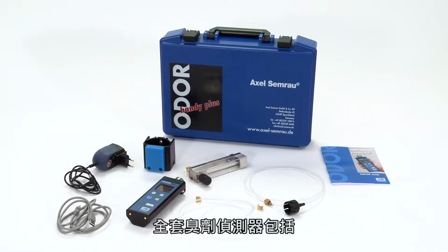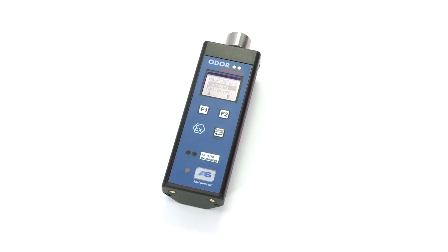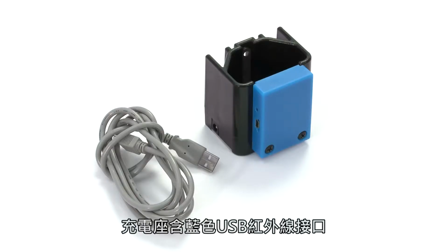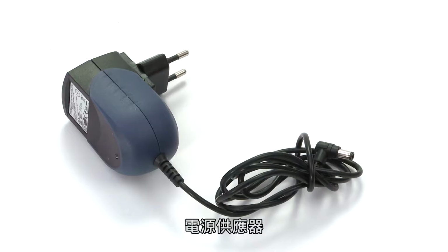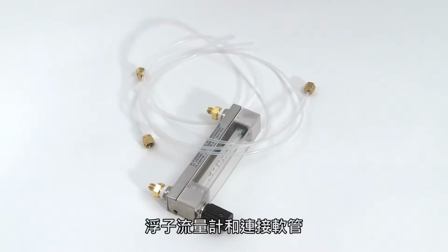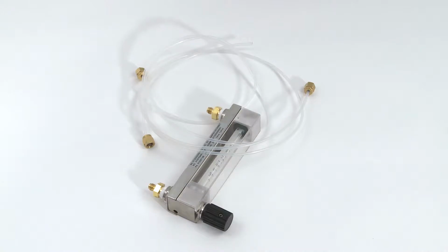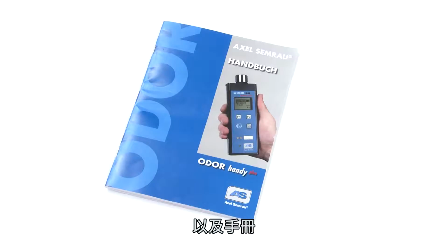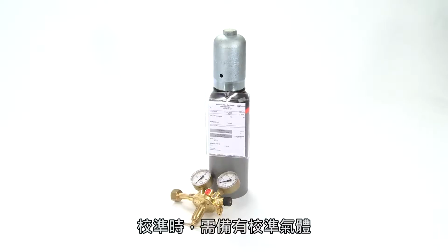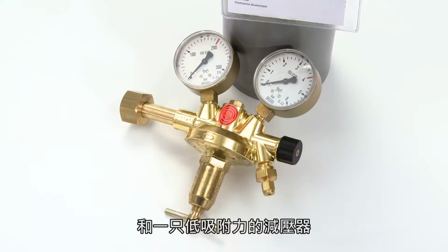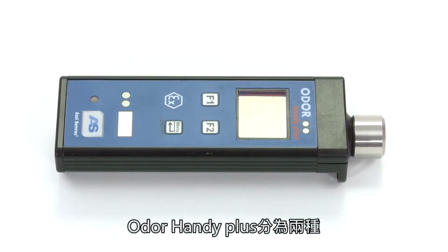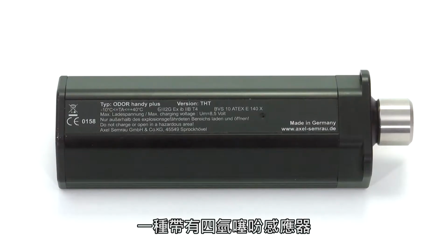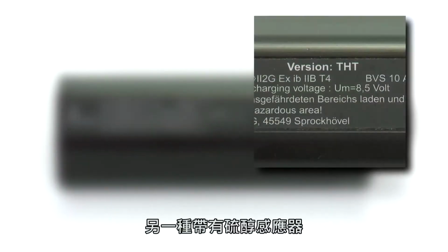The complete set consists of the measuring instrument, charging station with the blue USB infrared interface, power supply unit, rotameter and connecting tubes, measuring cap, and manual. For the calibration, you will need a calibration gas with a low absorption pressure reducer. The Odor Handy Plus is available in two versions. One version with the THT sensor and one version with the mercaptan sensor. There is no difference in operation.